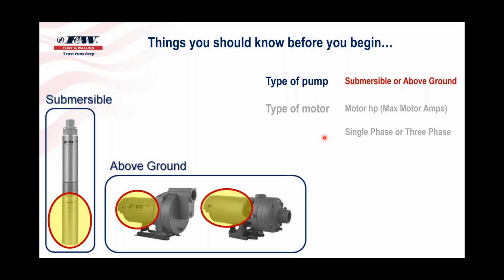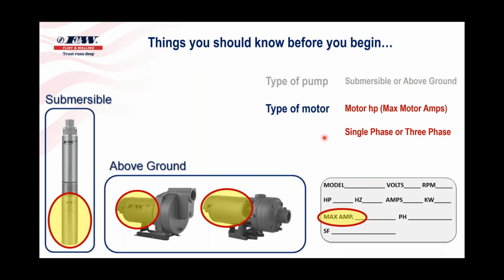What kind of a motor is it going to operate, a submersible or an above ground? And then when we look at the max motor amps, every motor is going to have a nameplate or a data plate on it somewhere, and it's going to give you a lot of information in regards to that motor. It's going to tell you the volts, the RPM, the hertz, the horsepower, and on there somewhere is going to be max amps. And that's the number that we're looking at. So I'm not looking to plug in 1.5 horsepower per se. I'm looking at what is the max amps for that 1.5 horsepower motor. That's what I'm going to plug in there. So hopefully we've got that kind of drilled home. And again, single phase or 3-phase.